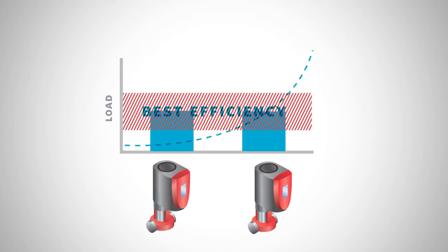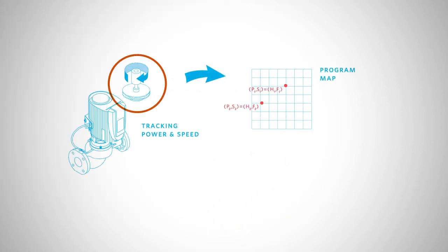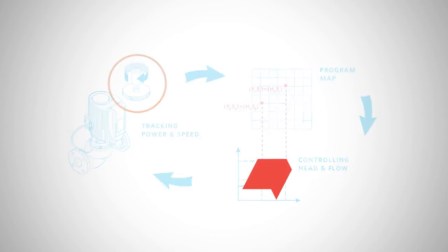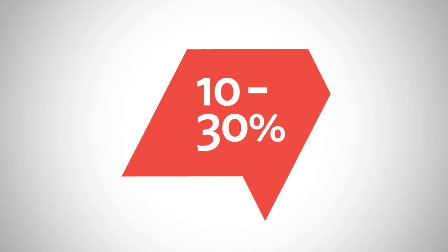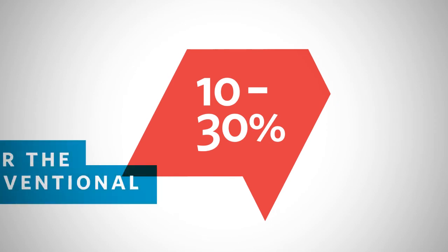Armstrong's parallel sensorless pump control is an algorithm embedded in the pump controller that stages multiple pumps on and off and regulates pump speed based on the best efficiency. This control approach saves an additional 10 to 30% in operating costs over conventional speed-based staging.